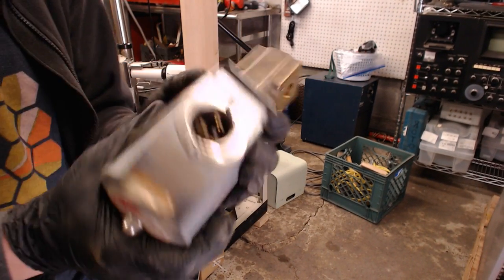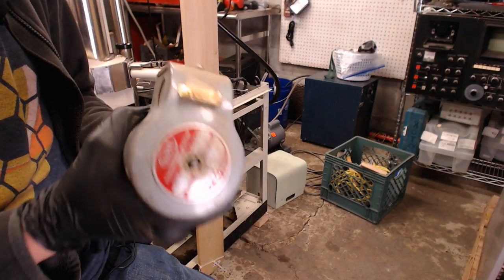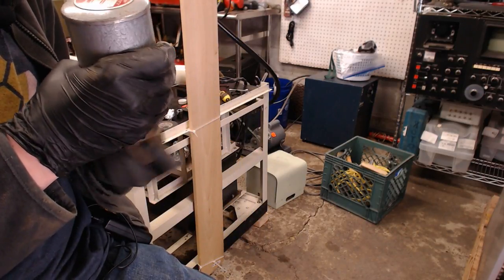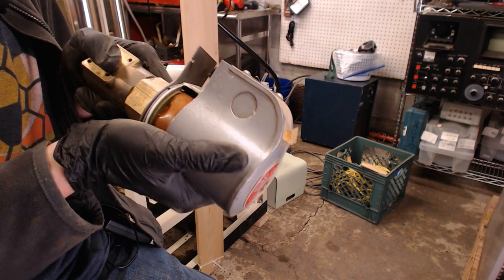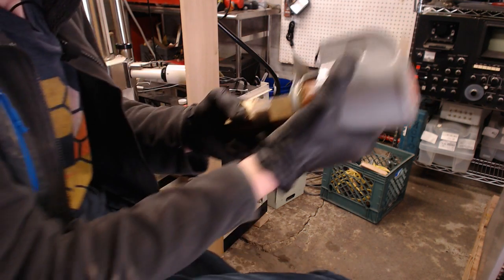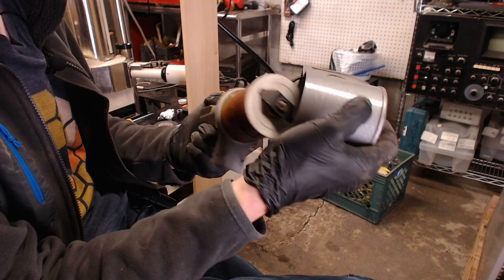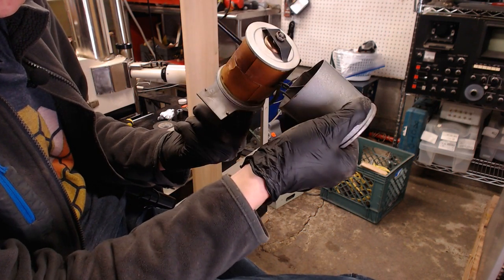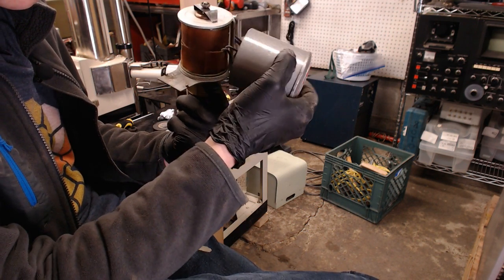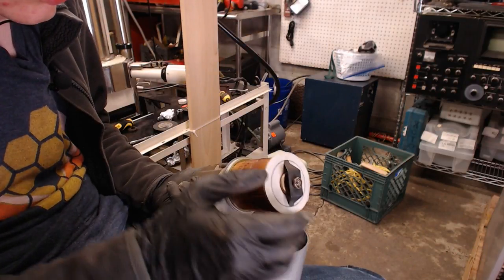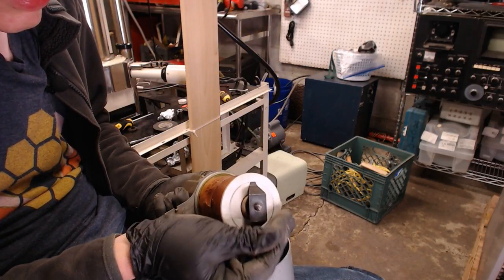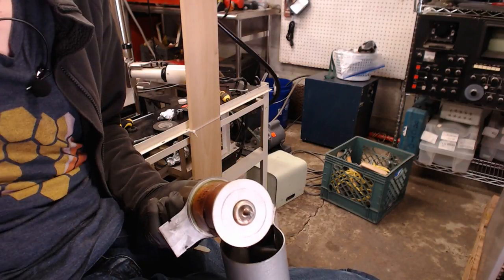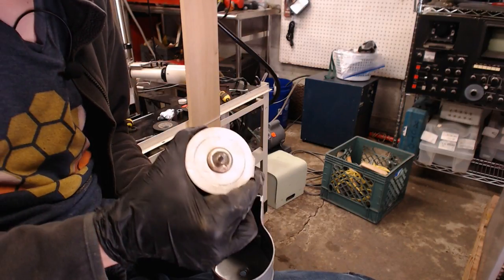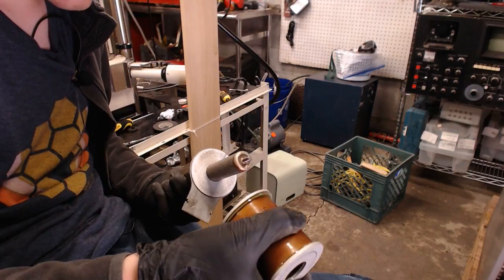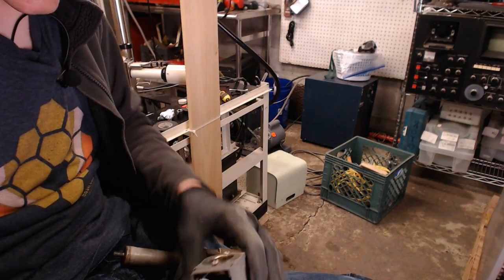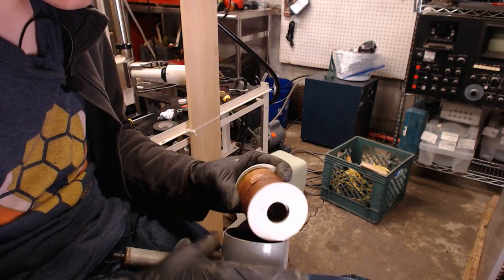Okay, so here's the valve. Twisting it. Nope, that came off. Okay. So it's an electromagnetically driven valve, so a solenoid valve. So that's the big coil right there. There's a nut right there, so we pull that nut off. That retaining clip probably comes off. And that whole coil comes off. And this thing just operates at 120 volts AC.